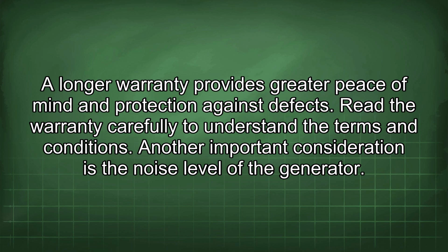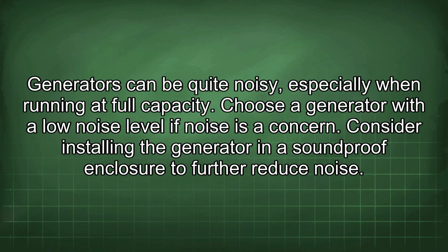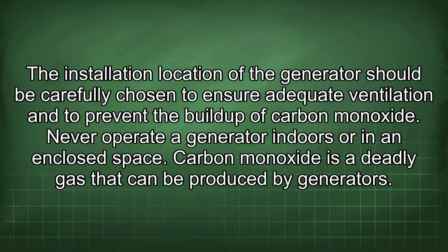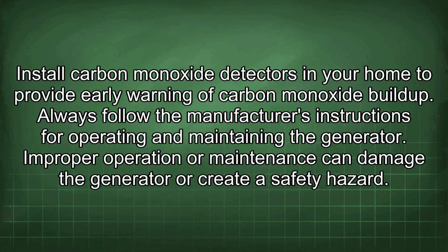Another important consideration is the noise level of the generator. Generators can be quite noisy, especially when running at full capacity. Choose a generator with a low noise level if noise is a concern. Consider installing the generator in a soundproof enclosure to further reduce noise. The installation location of the generator should be carefully chosen to ensure adequate ventilation and to prevent the buildup of carbon monoxide. Never operate a generator indoors or in an enclosed space. Carbon monoxide is a deadly gas that can be produced by generators. Install carbon monoxide detectors in your home to provide early warning of carbon monoxide buildup.